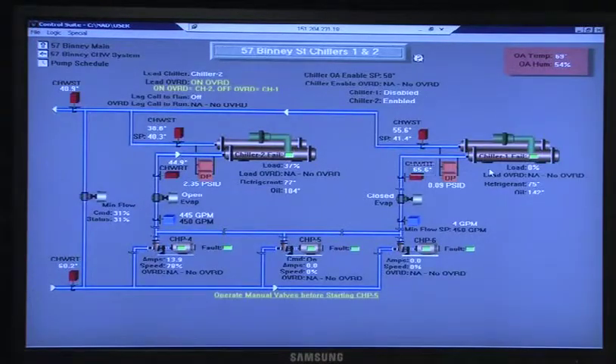These are the two chillers. Lead chiller number 2. What is it, lag call to run is off, that's off. Lead chiller number 2. If you have extreme conditions, you may have to run 2 chillers. So that lag call to run is just gonna give you an indication in the program, when I wrote the program for them, that something is calling the lag one to run, whether or not one can't maintain temperature. Primarily the one chiller is gonna run. If one fails, the other one will end up starting based on the timing and the temperatures.